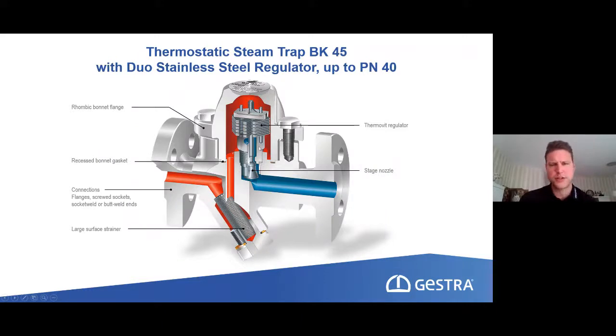But if we think of a BK like we see here, we have the very big advantage that the lifetime of such a bimetallic steam trap is rather long. So if we have, let's say, a BK 45, it depends a little bit on the pressure we are operating at, but it could last for 15 years. This is possible, up to 15 years. It depends a little bit on the condensate quality and whether we have dirt or not. This is something that we have to admit.